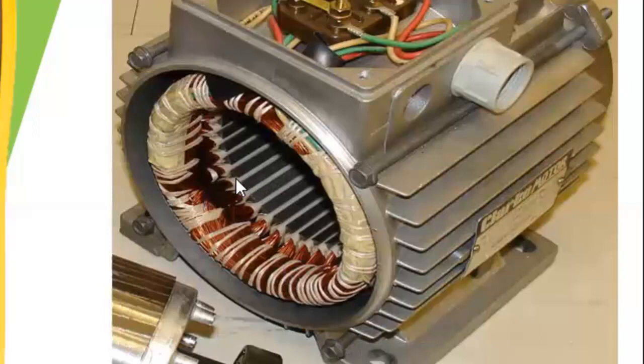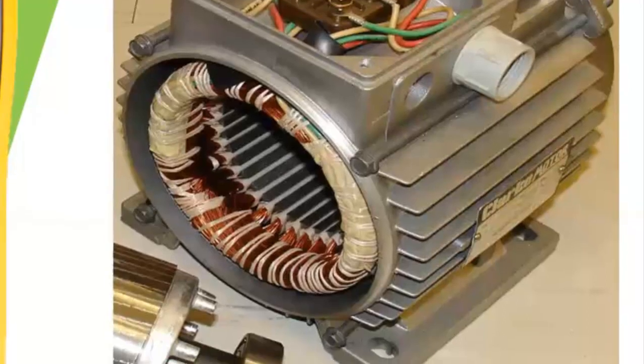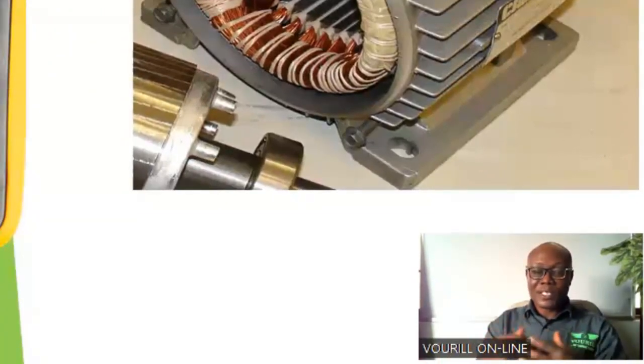But if there is failure in any of this insulating material, due to maybe overheat or short circuit within the slot, that can cause failure in those insulating materials and eventually cause a turn to ground short. And once there is a turn to ground short, of course, it has safety implications, because the personnel working on it will be exposed to a shock hazard.